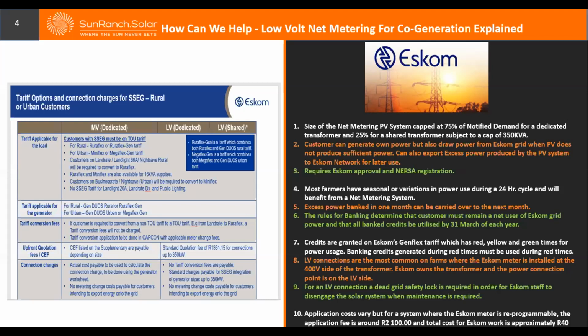Now, the difference in your budget quote all depends on what type of meters are currently installed. If you already have smart meters installed - the ones that usually have a modem already connected to the distribution box on the Eskom side - you're looking at an all-in Eskom cost of 20,000 Rand, and between 60 to 80 days for Eskom approval and installation from the date the application starts.